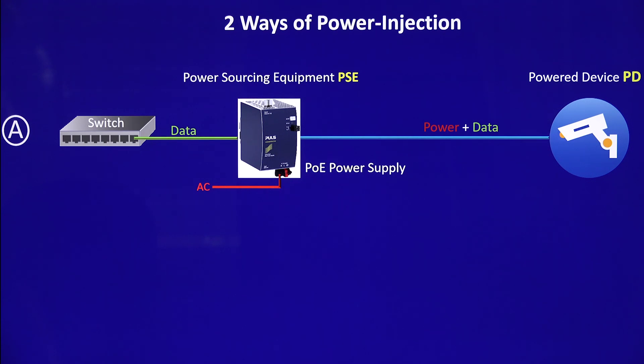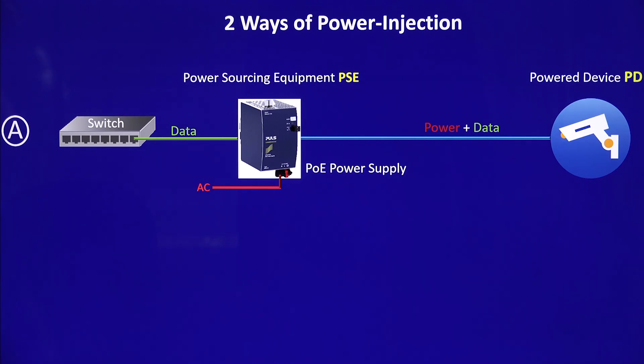How is the power injected into the RJ45 cable? There are two ways of doing it depending on the situation you have on the shop floor. The first situation is when you only have AC grid available. In this case, you can use a power supply with a built-in PoE injector, and this injector will push the power into the existing RJ45 cable and deliver the power to the PD.